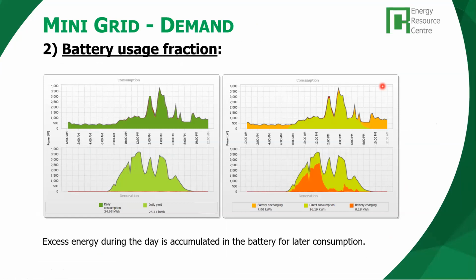Another aspect that we need to consider, if you remember, is the use of the batteries. The excess generation during the day is stored in the battery for later consumption. In this example, from a real community in West Africa, we can see this is the consumption. This is a community with a lot of productive activities. You see the peak is mostly during the middle of the day, and this is the solar generation curve. So this is when the PV panels are generating. So you can see for this day, the electricity that was consumed and the electricity that was generated by the PV panels was more or less the same.